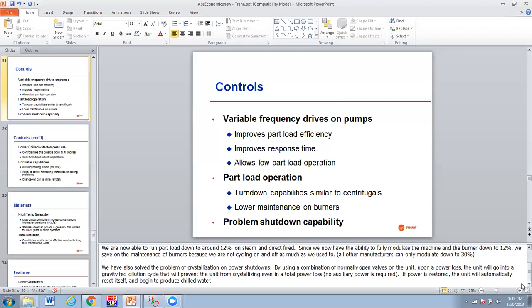We have also solved the problem of crystallization on power shutdowns by using a combination of normally open valves on the unit. Upon power loss, the unit goes into a gravity-fed dilution cycle that will prevent the unit from crystallizing even with a total power loss. And so you don't need auxiliary power. When power is restored, the unit will automatically reset itself and begin to produce chilled water.